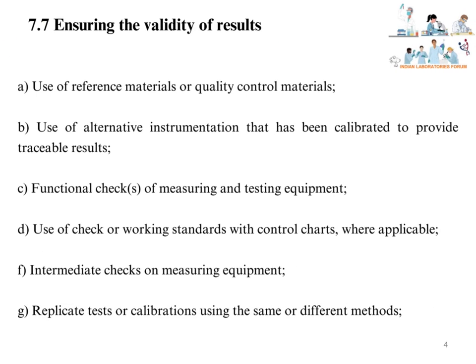Use of reference materials or quality control materials, such as reference material or quality control material with a certified reference value. Use of alternative instrumentation that has been calibrated to provide traceable results. If a laboratory has two or more similar equipment, it can use calibrated alternative instruments for comparison of results.